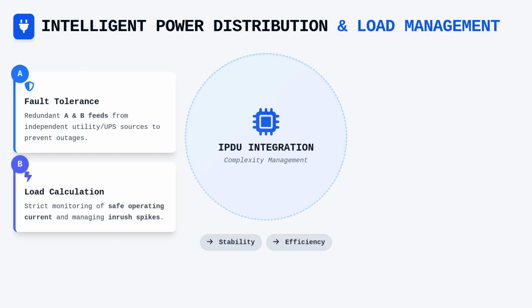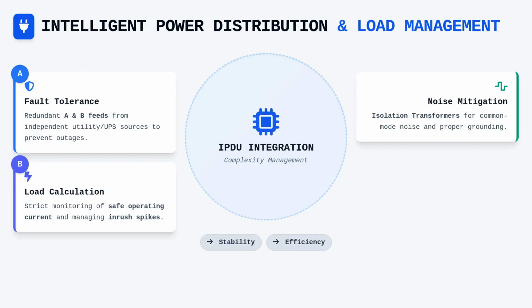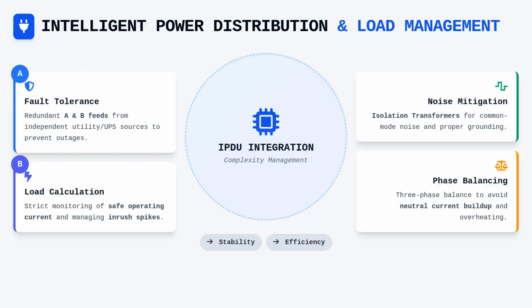You must calculate the load on each branch circuit carefully, ensuring that neither the A nor B feed exceeds the safe operating current of the distribution path. Especially when considering the inrush current of power supplies. The use of isolation transformers is another critical consideration, specifically for mitigating common mode noise and maintaining proper grounding references within sensitive digital circuits.